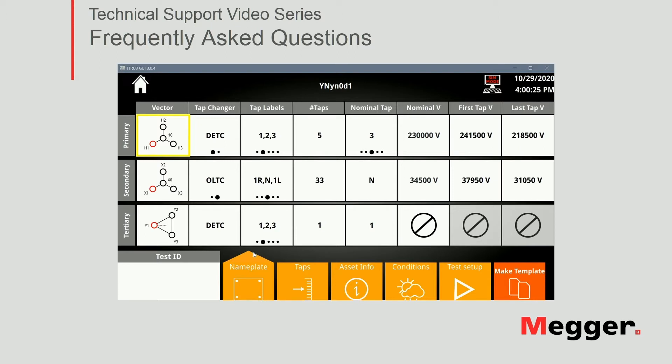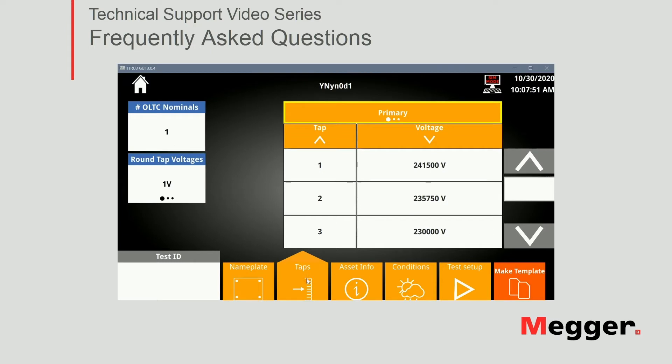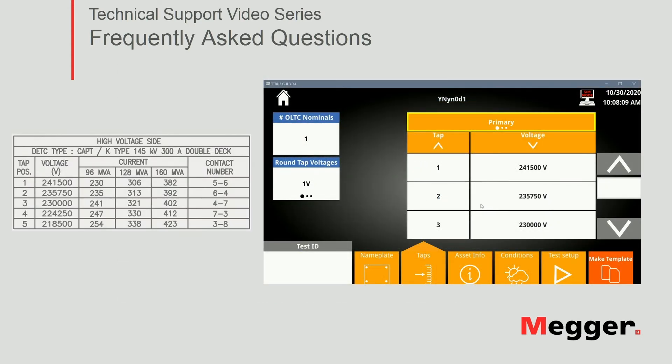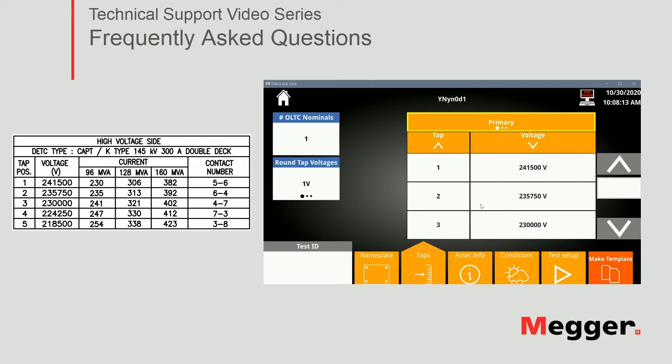Moving on now to the taps section of the test plan. As I input the voltages for the first and last tap voltages, the software should have calculated all the steps for me. So all I have to do is really check that the calculations are correct. And the reason for me to check is that sometimes certain customers will request from the transformer manufacturer they round the tap voltages, so those steps wouldn't be even or equally spaced.